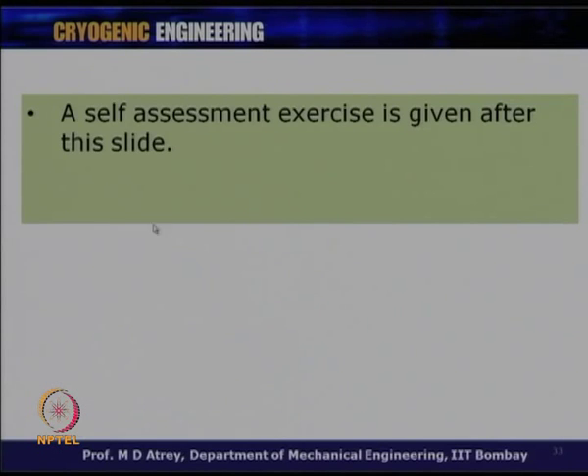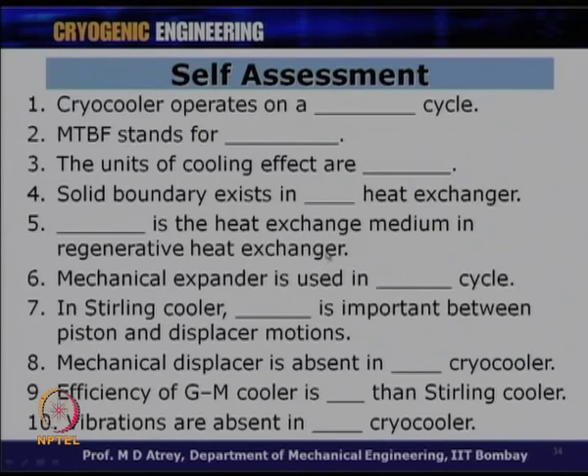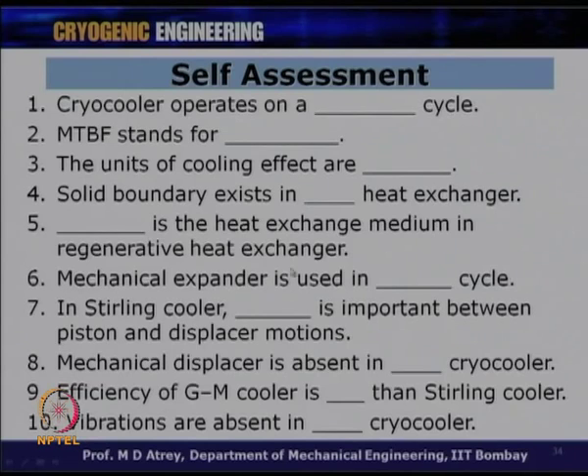In summary: a cryocooler is a mechanical device generating low temperature via compression and expansion of gas. Cryocoolers are needed because they eliminate cryogen requirements, offer reliable operation, and while cryogen costs are increasing, cryocooler costs are decreasing. Heat exchangers are either regenerative (indirect heat transfer — Stirling, GM, Pulse Tube) or recuperative (direct heat transfer — JT, Brayton, Claude). Applications span space, gas, medicine, and superconductivity. Self-assessment exercises are provided — please go through them and assess yourself honestly.